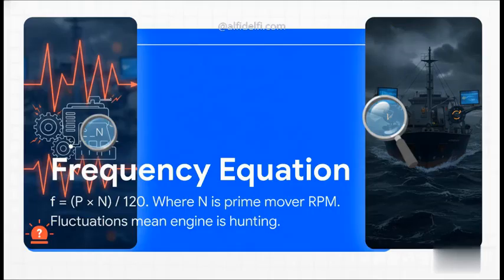Section 3. Technical causes and diagnostics. Now, the underlying math tells the whole story here. Frequency, which is F, equals P, the number of poles, multiplied by N, the RPM of the prime mover, all divided by 120. Because the number of poles on your machine is fixed, a wildly swinging frequency mathematically proves that N, your engine's RPM, is hunting. Your mechanical governor is failing you, and because of this, the entire ship suffers. You'll see motors running erratically, sensitive electronics tripping out, and your steering gear hunting. It affects the whole shebang.